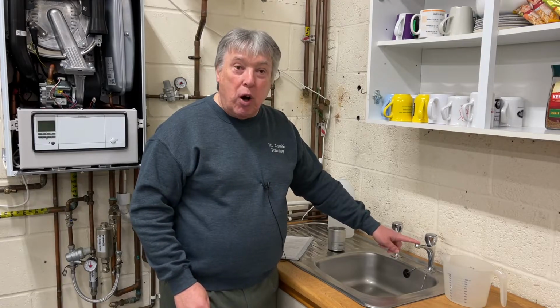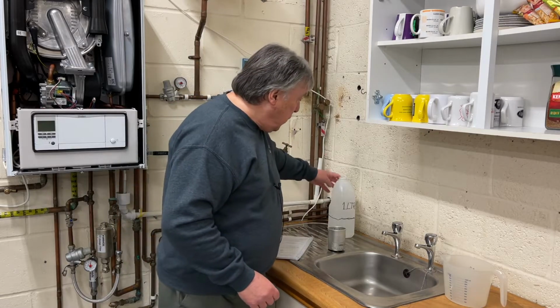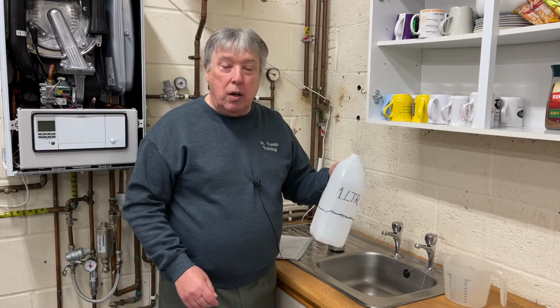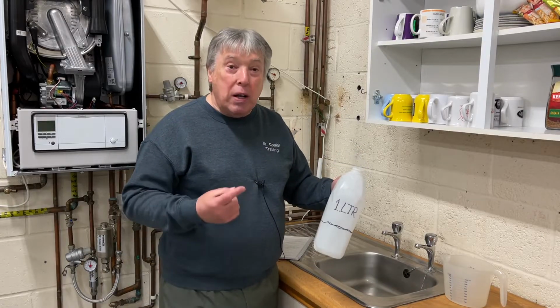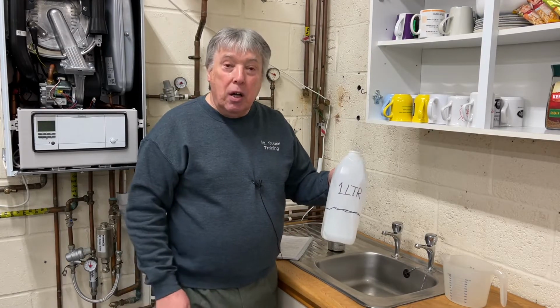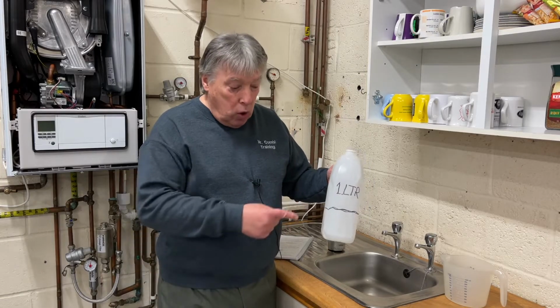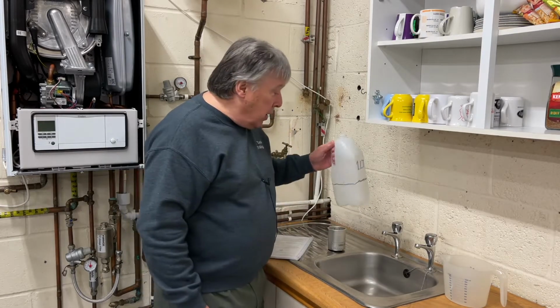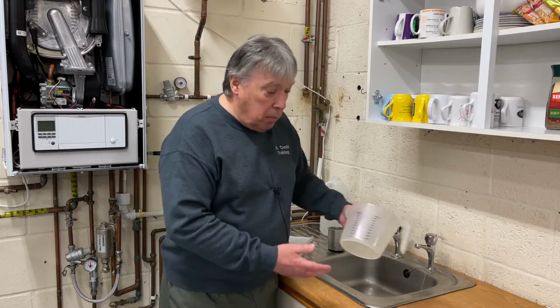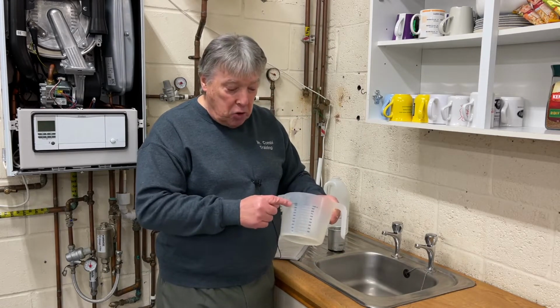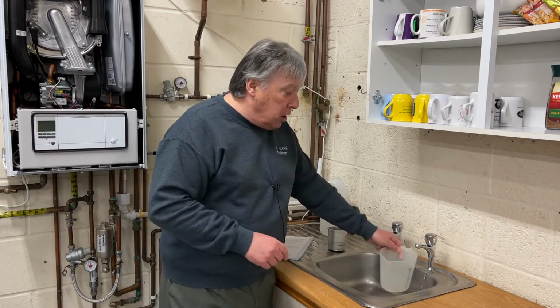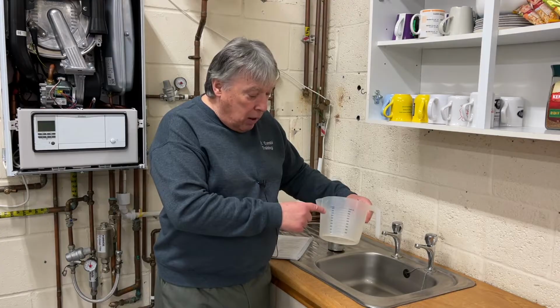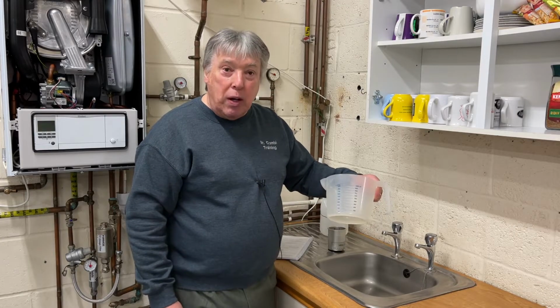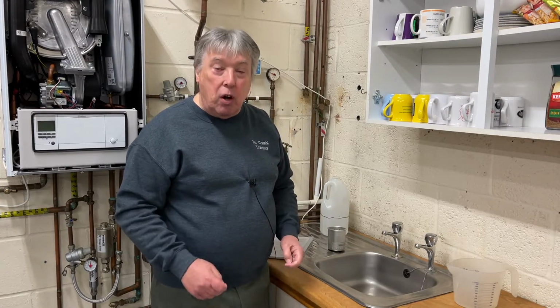We have to measure that we've got adequate flow going in, and there's various ways we can do this. If you have enough room, there's a 2 litre empty milk bottle, or better still a 1 litre, and then we're going to measure how many seconds it takes to reach that level. Another way, even better, is simply having a measuring jug which goes to 1 litre, and again we'll put it underneath the cold tap full on, and then we'll count how many seconds it takes to reach 1 litre, and then divide that figure into 60, and that will give us the answer of the flow rate.